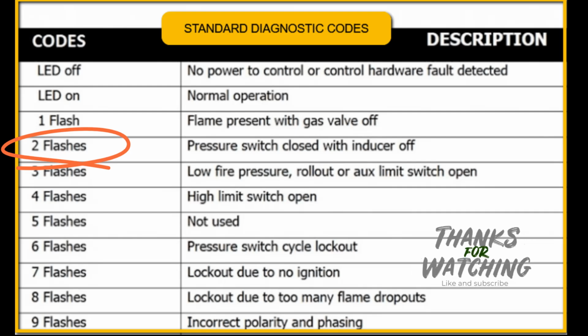On a high-efficiency furnace, it is the inducer motor that pressurizes this switch to enable it to allow the furnace to run. So that said, it is often an inducer issue that throws this code. If it is humming and or very hot to the touch, it could be seized or blocked. If you need to remove the inducer motor, then see our videos on that process. Check the condensate trap and piping for restrictions. We have a video on this.